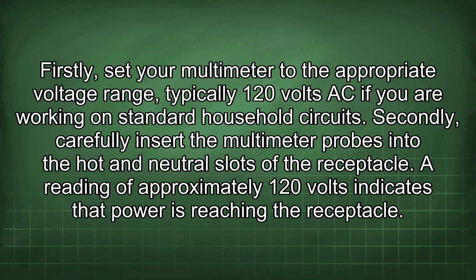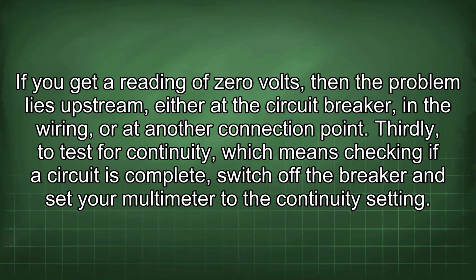Now let's delve deeper into using a multimeter for troubleshooting. Firstly, set your multimeter to the appropriate voltage range, typically 120 volts AC if you are working on standard household circuits. Secondly, carefully insert the multimeter probes into the hot and neutral slots of the receptacle. A reading of approximately 120 volts indicates that power is reaching the receptacle. If you get a reading of 0 volts, then the problem lies upstream, either at the circuit breaker, in the wiring, or at another connection point.